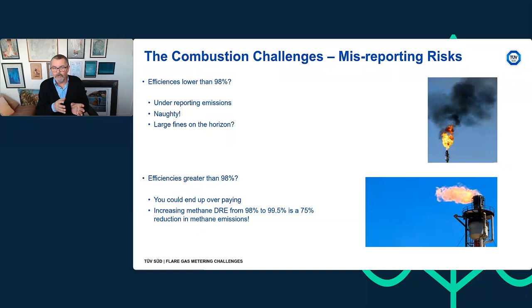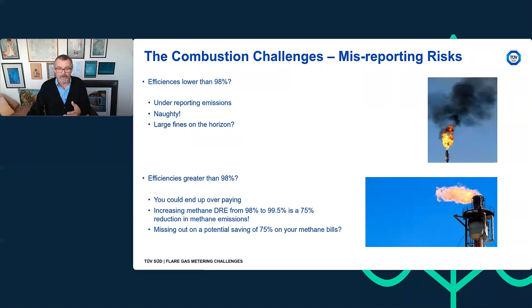We have to remember that if I increase my methane destruction and removal efficiency from 98 to 99.5%, that's only a 1.5% increase, but it's a 75% reduction in my methane emissions. It's a huge reduction in my methane emissions. So as regulations evolve and as perhaps a price is put on emitted methane, am I missing out on a potential 75% saving? Who knows?